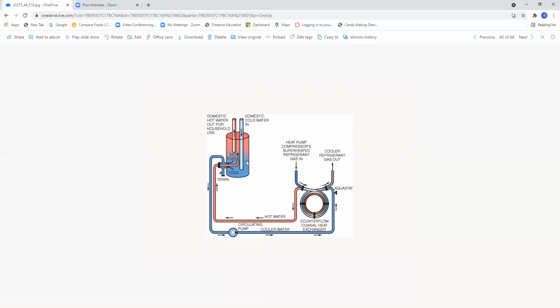This is a domestic hot water loop showing the counterflow coaxial heat exchange. The water is heated by the refrigerant loop. So basically, this is a domestic hot water heater. Here we have a counterflow coaxial heat exchanger. The heat pump compressor, superheated refrigerant goes through here, cooler gas comes out. So basically, we're using the waste heat off of the heat pump or air conditioning unit to create a heat source to heat this water up. So this is going to assist with reducing the use of a fossil fuel such as natural gas to heat hot water for domestic use, by utilizing the compressor.